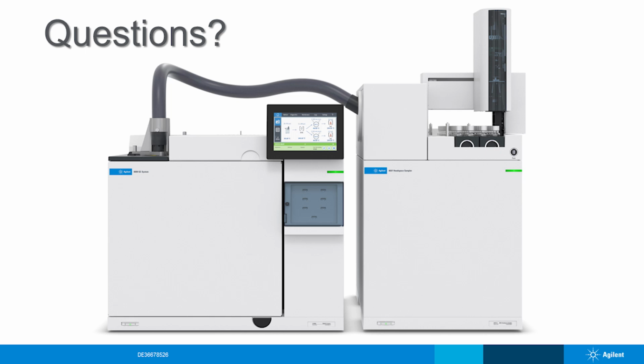Yeah, so I don't remember the max temp off the top of my head, but I can follow up with this one in email. If you have the sleeve, you should be able to see it when you pull it. I mean, you'd have to release your transfer line, but it should be coming out of the GC side of your transfer line.